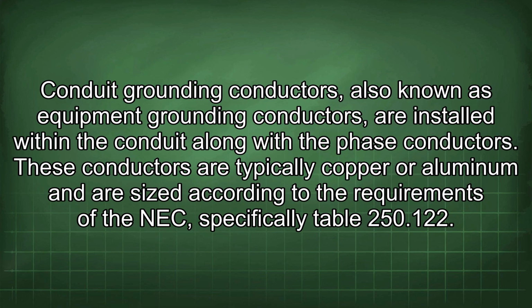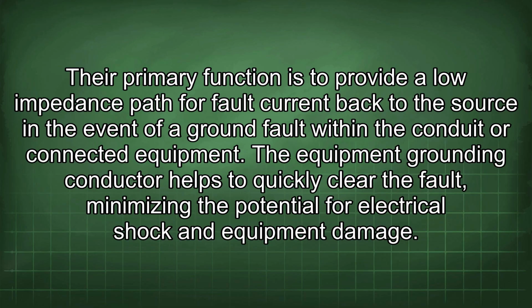Conduit grounding conductors, also known as equipment grounding conductors, are installed within the conduit along with their phase conductors. These conductors are typically copper or aluminum and are sized according to the requirements of the NEC, specifically Table 250.122. Their primary function is to provide a low-impedance path for fault current back to the source in the event of a ground fault within the conduit or connected equipment. The equipment grounding conductor helps to quickly clear the fault, minimizing the potential for electrical shock and equipment damage.